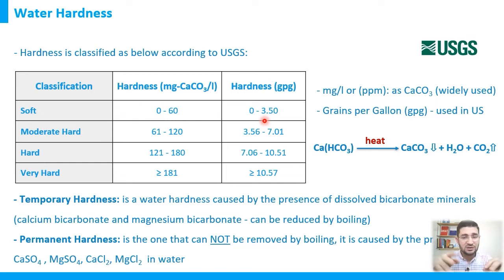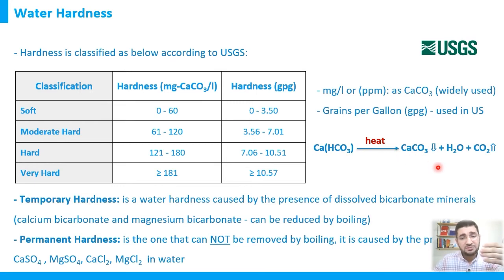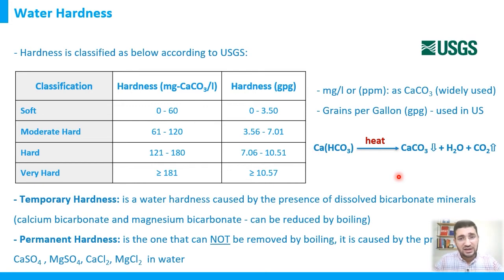When water contains hardness in the form of calcium bicarbonate — Ca(HCO3)2 — applying heat causes calcium carbonate to precipitate and carbon dioxide to evaporate, producing water. This means that increasing temperature or boiling hard water causes calcium carbonate precipitation. This is the key principle behind scaling inside pipelines, heat exchangers, and steam generation systems.